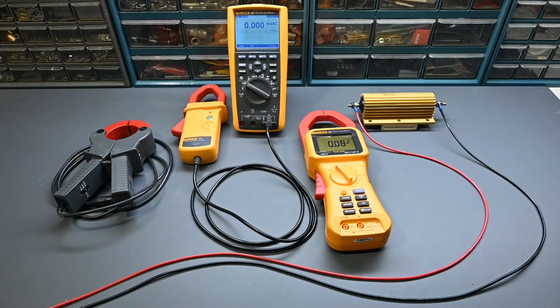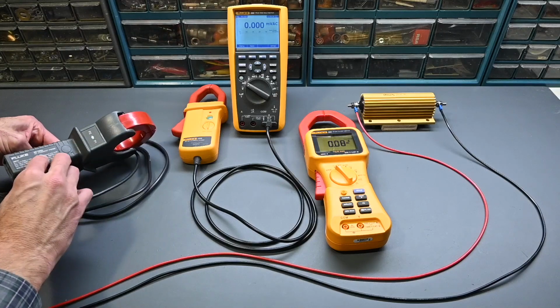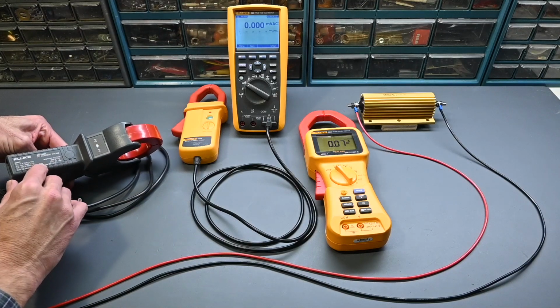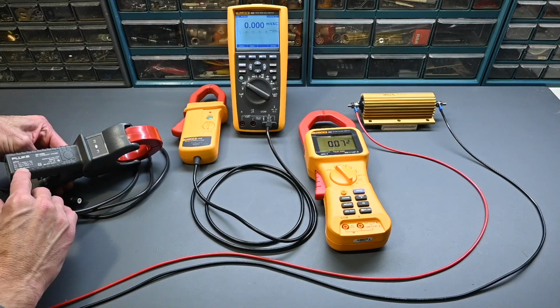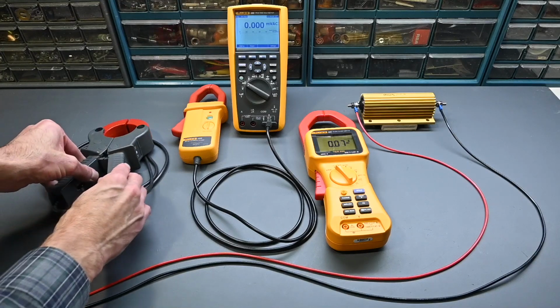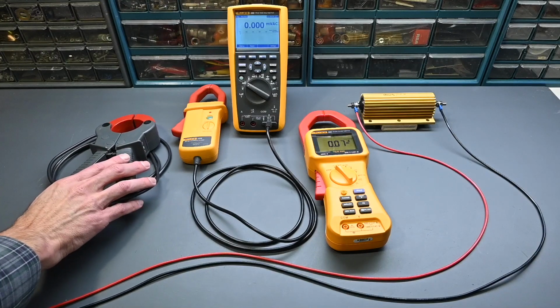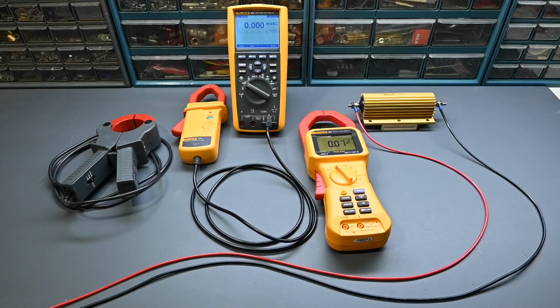Now the AC current frequency needs to be within the range of the clamp. So on a clamp like this model, for example, it's a Fluke 80i 1000S. The frequency range is 5 Hertz to 100 kilohertz, so quite a wide frequency range. But of course you need to be within the frequency range no matter what it is on the clamps. If you're outside the frequency range, then they'll just end up dropping off and not have the correct response.